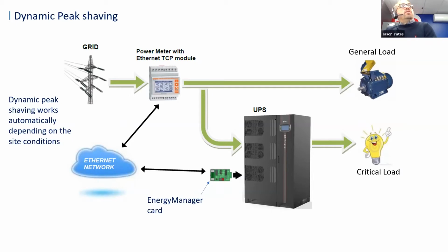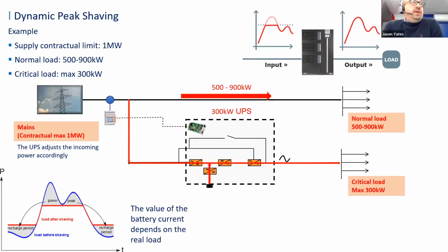Now, this was used on a site recently, whereby the contractual limit for the site was 1 megawatt. Their normal load, as you can see, typically moved around between 500 to 900 kilowatts. And they had a critical load with a maximum of around 300 kilowatts. In real terms, at full load, that would put 1.2 megawatts onto the incoming supply, which would go beyond the contract. So during these short durations, the UPS system was there to push that portion of power onto the batteries. When the power coming into the site was low, we could use that power to charge the batteries, and when it was high, we could take the power back from the batteries. So that's a good example of where we've used dynamic peak shaving.